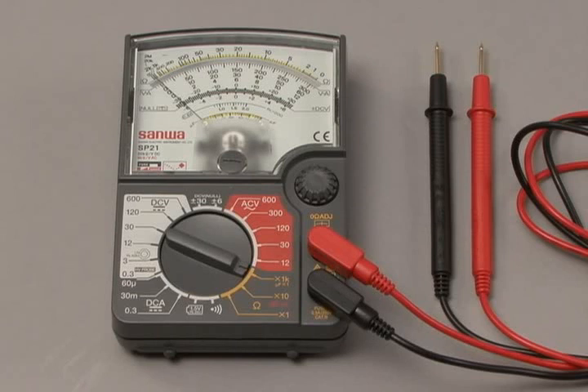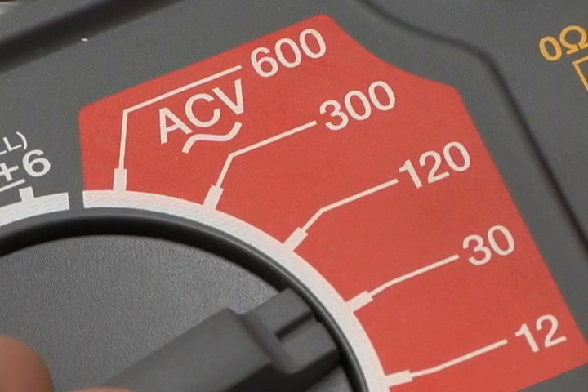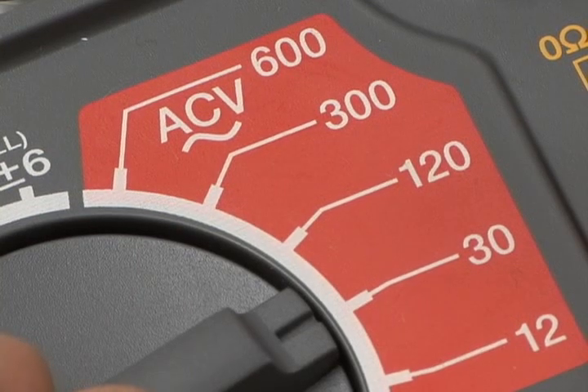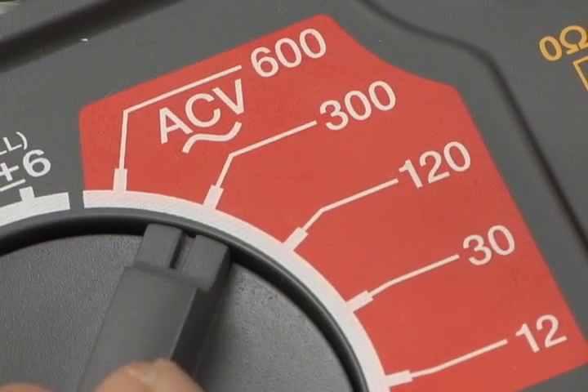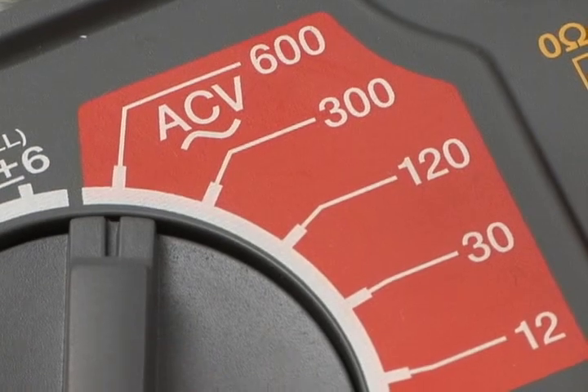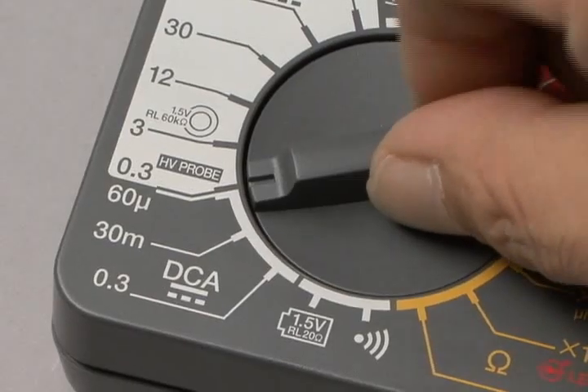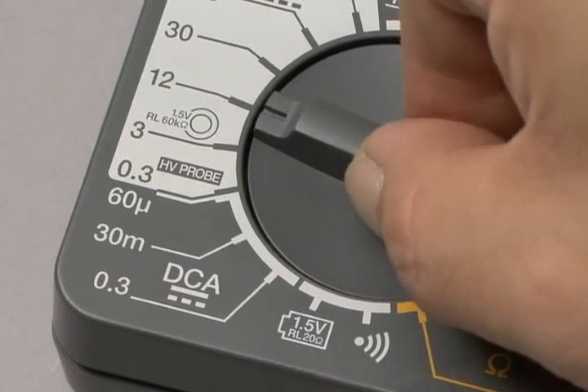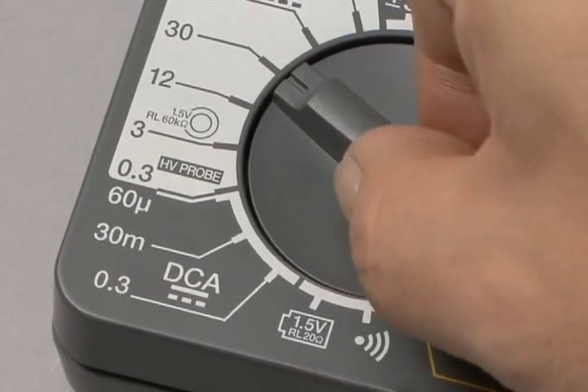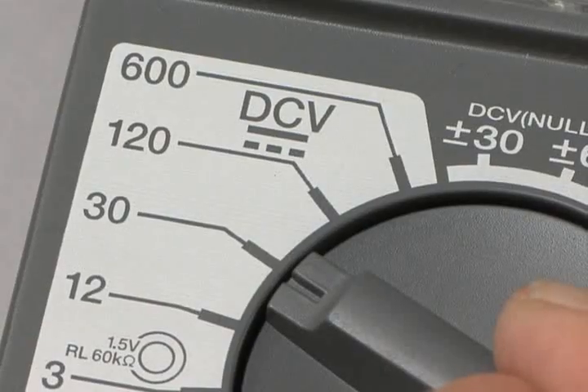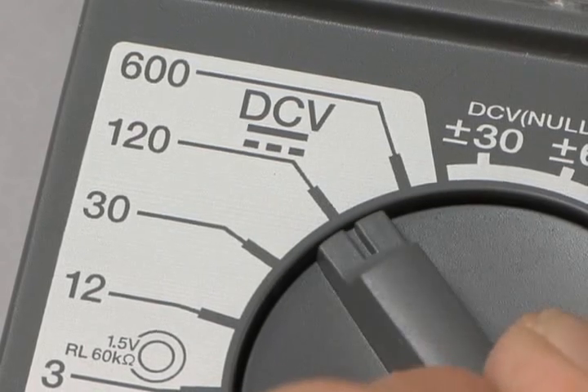A tester is used to locate defects by measuring the voltage of electrical equipment. To measure alternating current voltage, set the rotary switch to ACV. And to measure direct current voltage, set it to DCV. If the voltage range to be measured is not known in advance, set the rotary switch to the highest value in the measurement range.